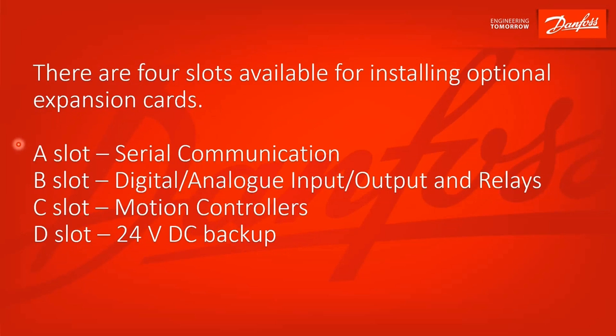If that's not enough, there are four option slots where you can add additional capability: A, B, C, and D. The A slot is where, if the built-in protocols are not covering what you need, you can add a serial communication option card. The B slot would be for hardware — digital and analog signals, either inputs or outputs, and relays. The C slot is for motion controllers, such as the advanced cascade controller or synchronizing and positioning controllers. The D slot is where you would add the 24 volt DC backup option to keep your drive's control card alive with 24 volts DC without line voltage being applied.